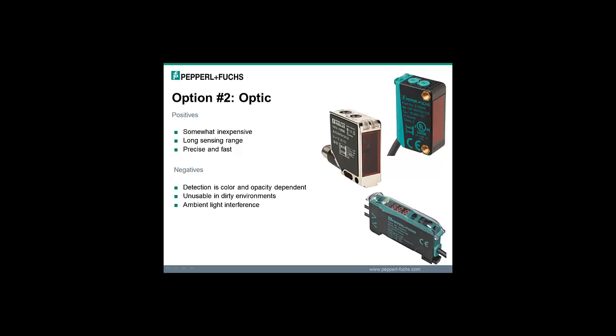Well, if inductives aren't going to work, in my opinion, the next option would be optics or photo eyes. They're also somewhat inexpensive. They have a much longer sensing range, so if you're looking to see a target at something longer than 50 millimeters, at a meter, 2 meters, 100 meters, photo eyes are a good option for that. They're very precise and very fast. The negatives for a photo eye, the detection is color and opacity, which is the clarity, like whether it's glass or it's not see-through. It's opacity dependent. It's unusable in dirty environments. If that lens gets clouded up, it's like trying to take a picture with a dirty lens. It's just not going to work. And the ambient light interference, if you've got any kind of fluorescent lighting and things, sometimes those can wreak a little bit of havoc with optical sensors.